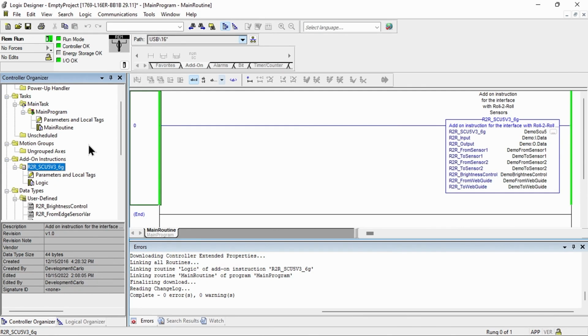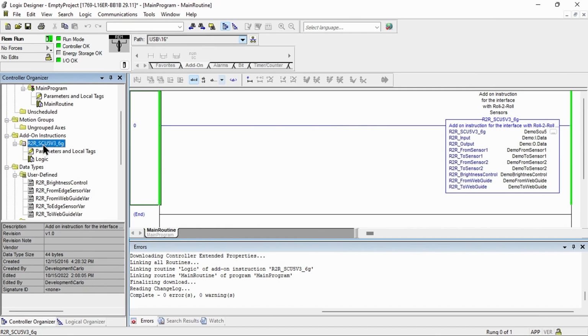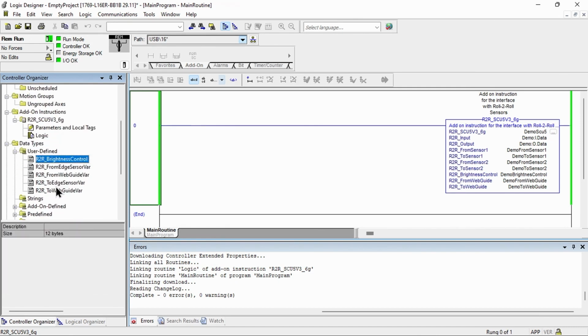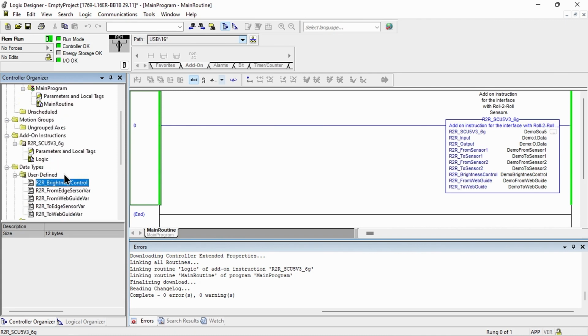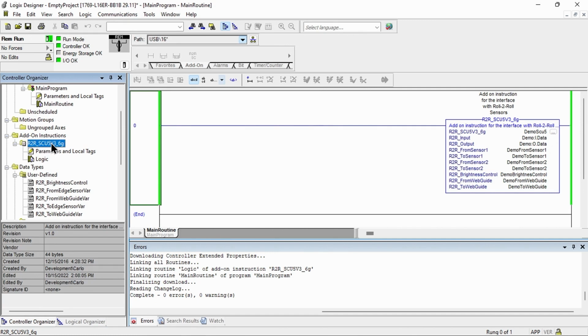One other problem that we have seen is that if you have installed an older AOI and you want to upgrade to a newer AOI, it's always best to delete the older AOI and delete all the user-defined variables, and install the new AOI from scratch, rather than trying to upgrade over the older one already installed on the system. And this covers all that I have for today.